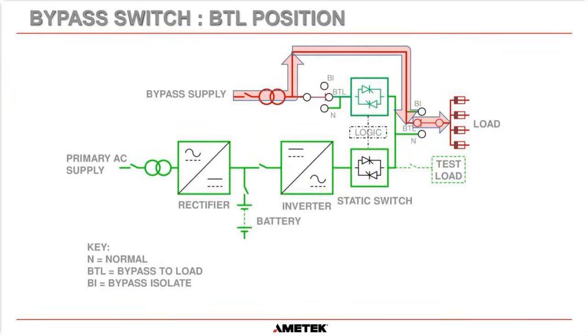Now, if we move to the bypass to load position, the first thing I'm going to say is always follow the procedure on your UPS, and that procedure will always tell you to first switch from the inverter static switch to the bypass static switch. There's usually going to be a push button on the front of your UPS that says bypass to load. Push that push button, this static switch will turn on, and then you move your bypass switch to the bypass to load position. And you can see here that now these two connections are connected. So now the power is flowing around here out to the load circuit. We still have power going to our static switch, and power would flow through here out to here.